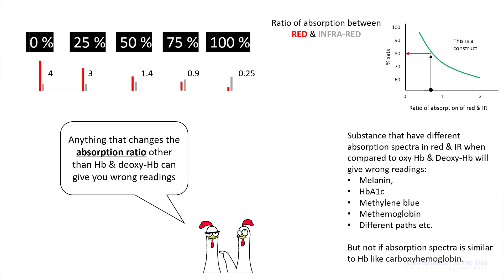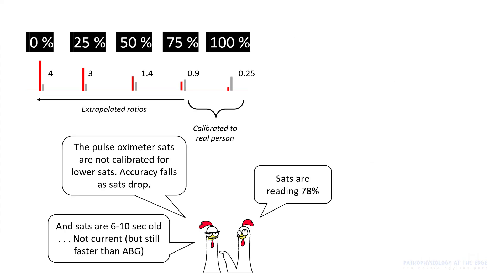Anything that changes the absorption ratio other than hemoglobin and deoxyhemoglobin can give you wrong readings. There are substances that have different absorption spectra in red and infrared, and those include melanin, A1C, methylene blue, methemoglobin, etc. Another important thing to remember is that pulse oximeters are not calibrated for lower SaO2 values — they have been calibrated in real persons only between 75 to 100%. Below 75%, these are extrapolated ratios.